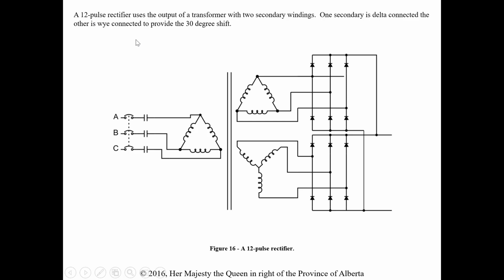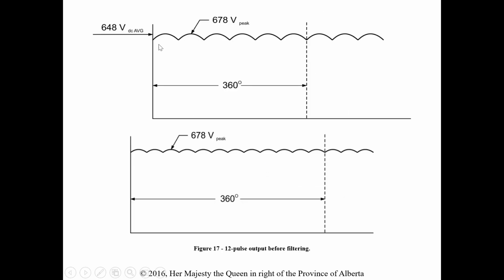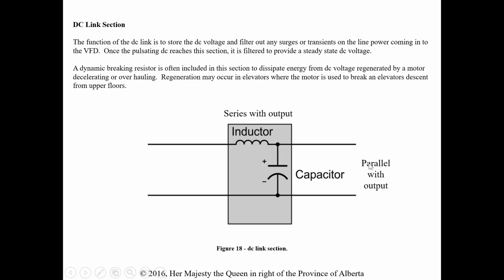What they say is for a 12 pulse, we're going to have the rectifier with 2 secondary windings, so that 30-degree shift. The way we can create that is by having 1 secondary in delta and 1 secondary in Y, and that'll give us our 30-degree shift and give us a 12-pulse rectifier. Now the difference between the 6 and the 12, we can see we have a lot smoother output in the same section here that we did when it was just 6. Okay, so we have basically a smoother DC coming out of there, less harmonics, before it's going to the DC link section for filtering.